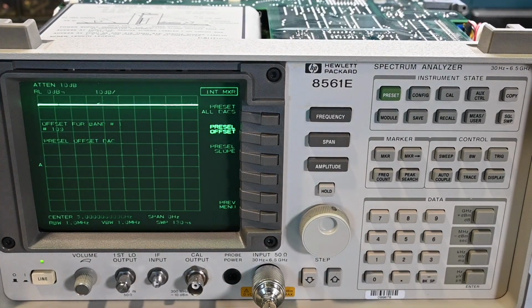Alright, so I had to go through the calibration procedure 7 times, and on the 7th time no further adjustment would peak the displayed trace. So then the calibration is complete at that point. So the actual values for the offset ended up being 70, then 90, 100, 104, 107, 108, and then 109. So you can see the numbers got a little bit closer as the calibration procedure went along. And then the slope values ended up being 157, 171, 178, 181, 183, 184. So it's complete at this point. Again, no further adjustments will peak that trace, so we're looking very good at this point.